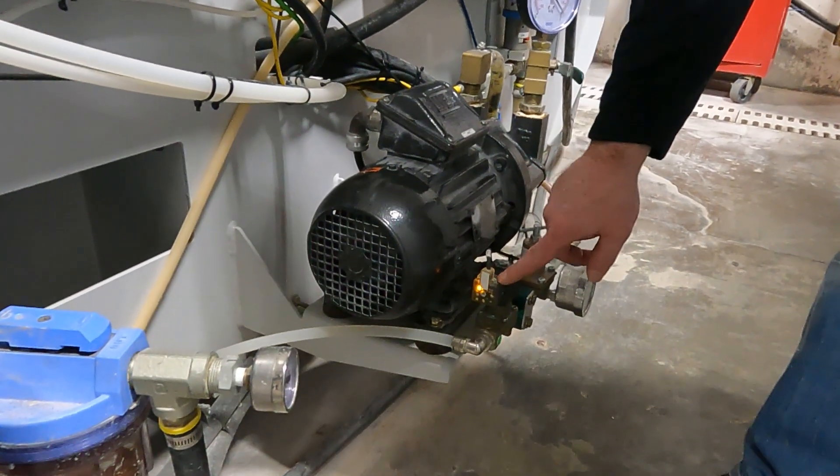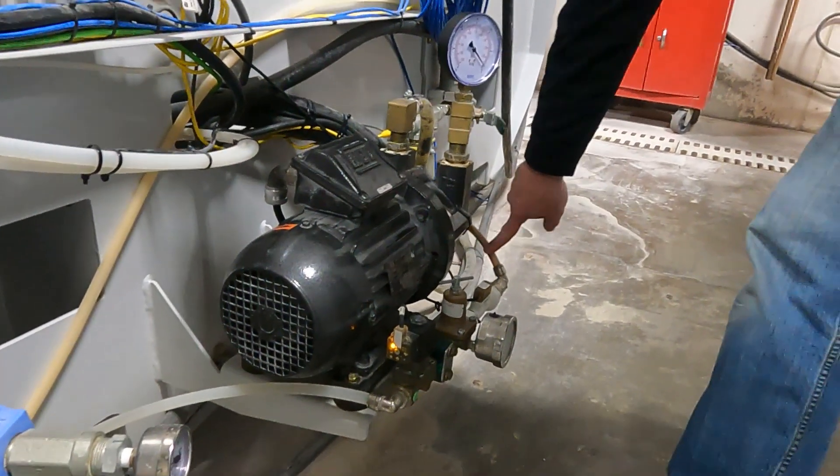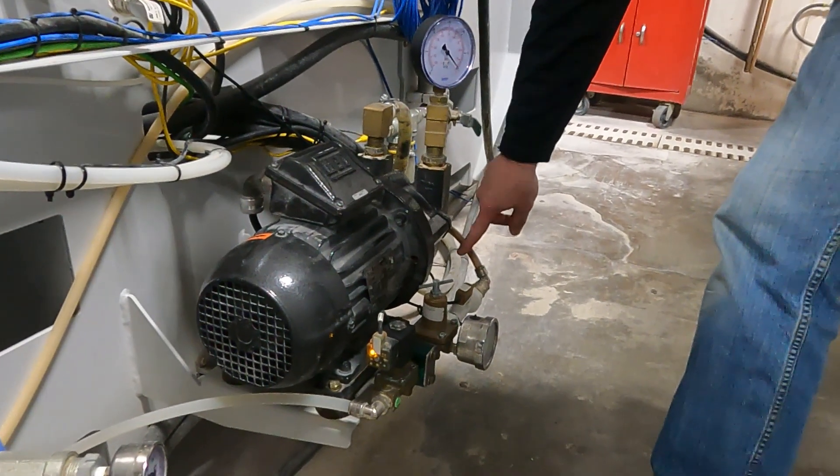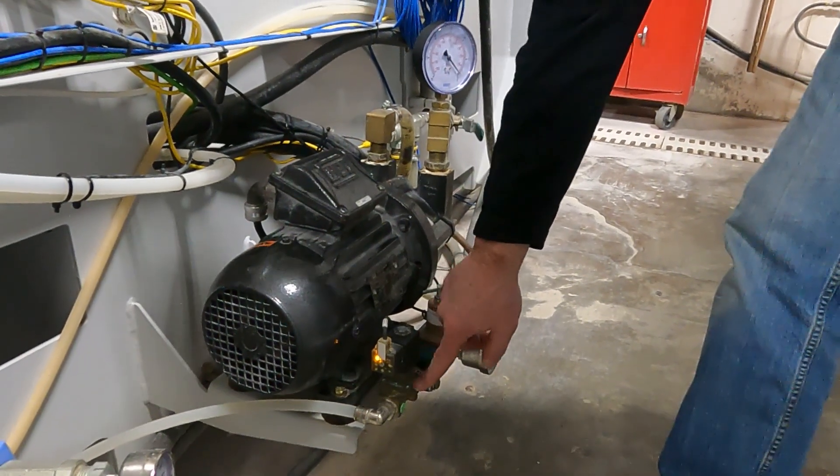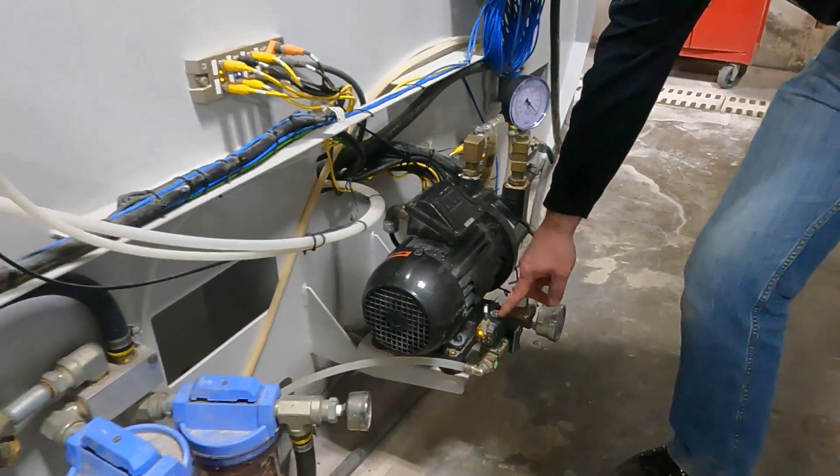If it does, you know you're getting power to that valve. If you're still not getting any water flow out here, then this valve is a problem and it's not turning that on.